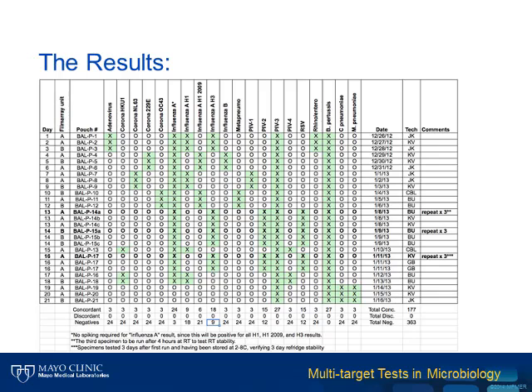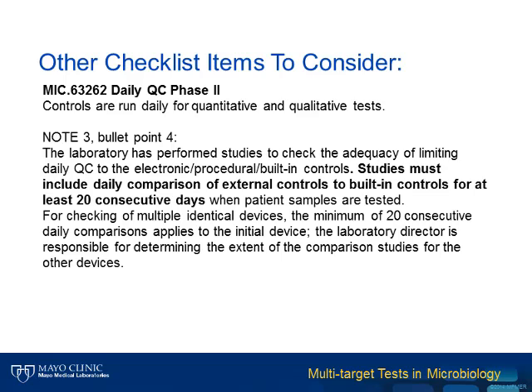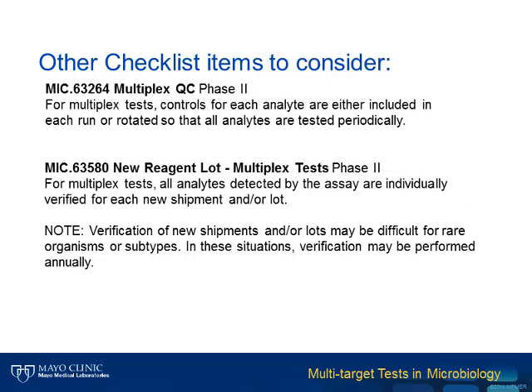Other checklist items to consider from the CAP checklist include the following. For a single cartridge or pouch type of setup, daily internal controls can be relied upon after the following study has occurred: external controls are compared to built-in controls for at least 20 consecutive days. By spreading our validation over three weeks, we met the 20-day requirement. If the multi-target assay is a plate type of setup, then multiple run controls may be necessary. If so, those should be rotated among all the analytes periodically.